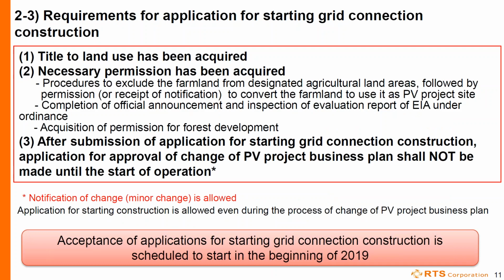Requirements to apply for starting grid connection construction are as follows: title to land use has been acquired, necessary permission has been acquired, and after submission of application for starting connection construction, application for approval of change to the project's business plan shall not be made until the start of operation. But a minor change, called notification of change, is allowed.